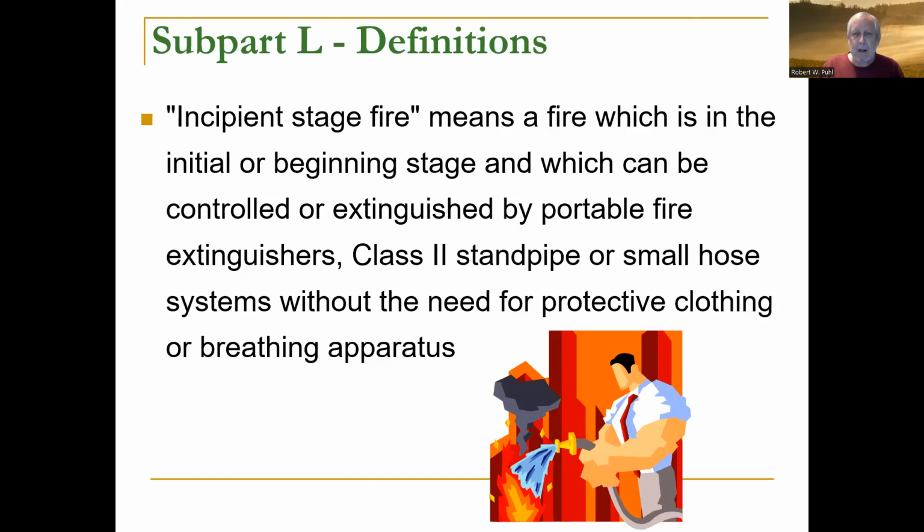Incipient stage fire, and that's a very common usage in talking about fire. Incipient stage means a fire which is in the initial or beginning stage and which can be controlled or extinguished by portable fire extinguishers, class 2 standpipe or small hose systems without the need for protective clothing or breathing apparatus.